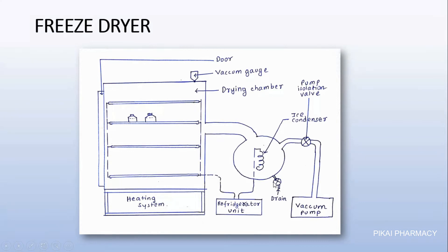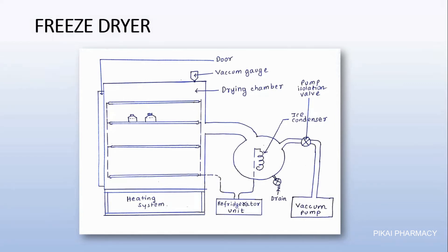From the beginning: the refrigerator unit decreases the temperature to a very low value where all the moisture content in the sample gets frozen and converted to ice. Then the vacuum pump is turned on to decrease the pressure, and then the heating system is turned on. This is called primary heating. Primary heating gradually increases the temperature, and with increasing temperature at low pressure, sublimation occurs — converting the ice on the sample to vapor. This vapor is collected by the ice condenser, converted to solid ice, and drained out through the outlet.